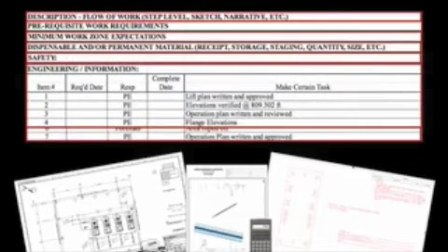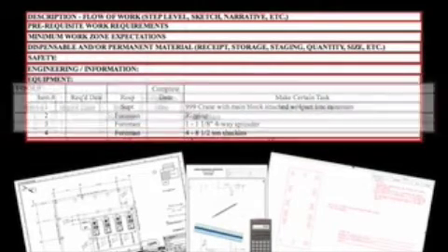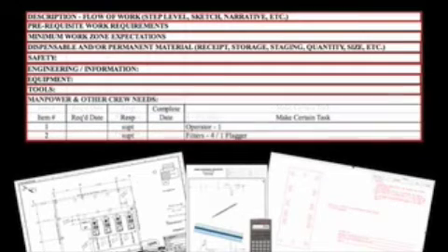Bowen's attention to detail promptly uncovered a dimensional error that could have caused major delays if not addressed proactively. One of the key factors that proves the importance of not only having that pre-plan, but also following through with the make certains and the checks that occurred with our bolts for the recycle pumps. We're using 2-inch diameter bolts, and it was discovered through our make certains that the original bolts fabricated for the site were fabricated approximately 2 inches short of what they should be. Guys, double check dimensions in the field.